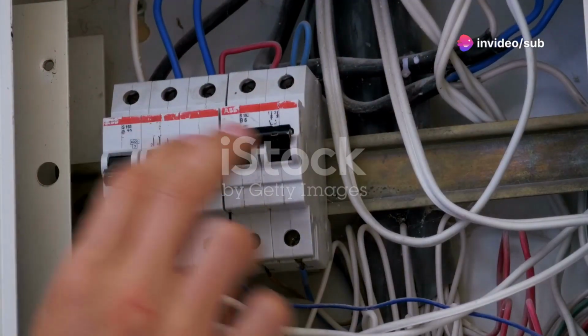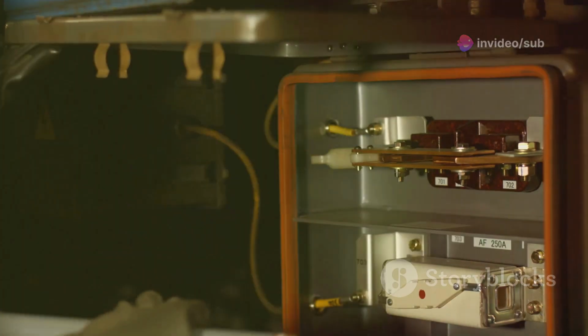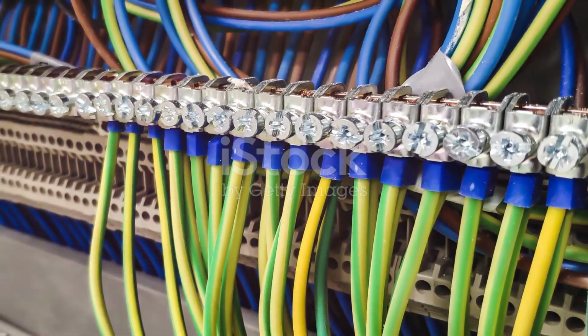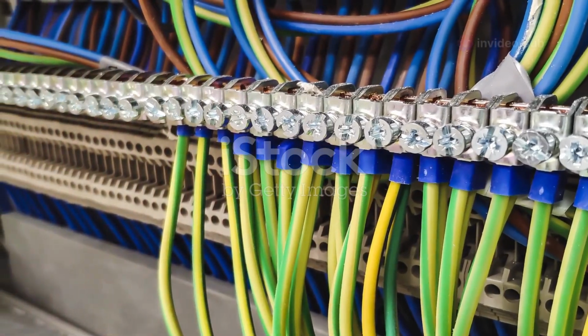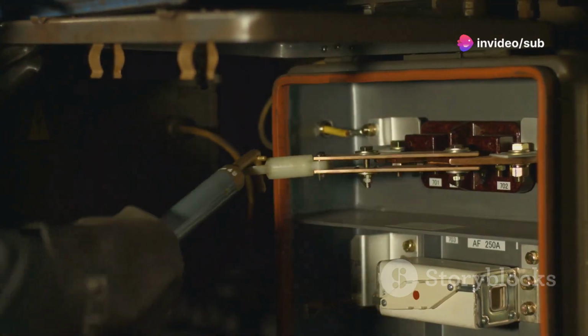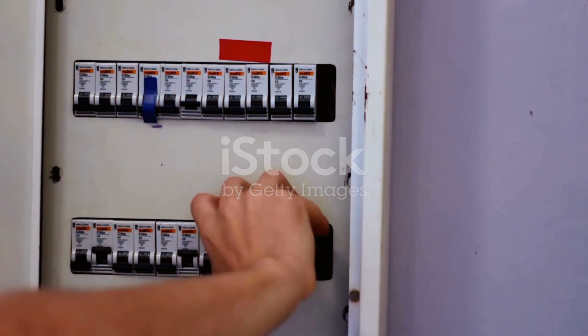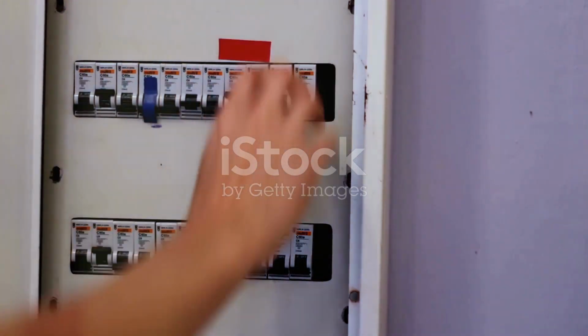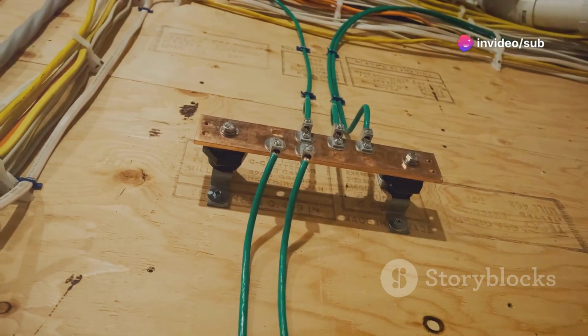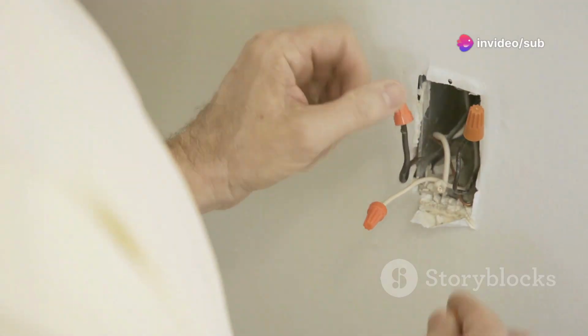Let's start with the basics. What are line and load terminals? The line terminal on a breaker is where power enters from the main supply or bus bar. You can sort of think of it as the entry door for electricity. The load terminal is where power flows out to your devices, lights, outlets, or appliances. In most breakers, you'll find one line terminal at the top or bottom and one load terminal on the opposite side. The line terminal gets connected to the source of power, like the big copper bus bar inside the panel. The load terminal delivers current to the branch circuit wiring.